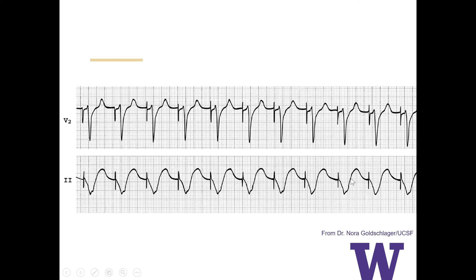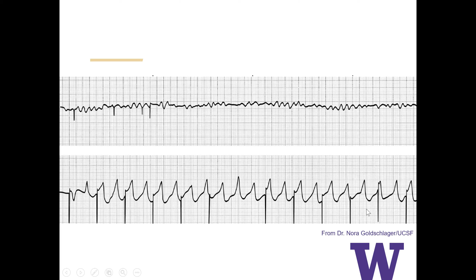This is an example of undersensing. So here on the top is essentially ventricular fibrillation. But then you can have these intermittent spikes. These are actually pacemaker spikes. And down here, this is ventricular tachycardia, and you can see that the pacemaker is undersensing the VT and is trying to pace.